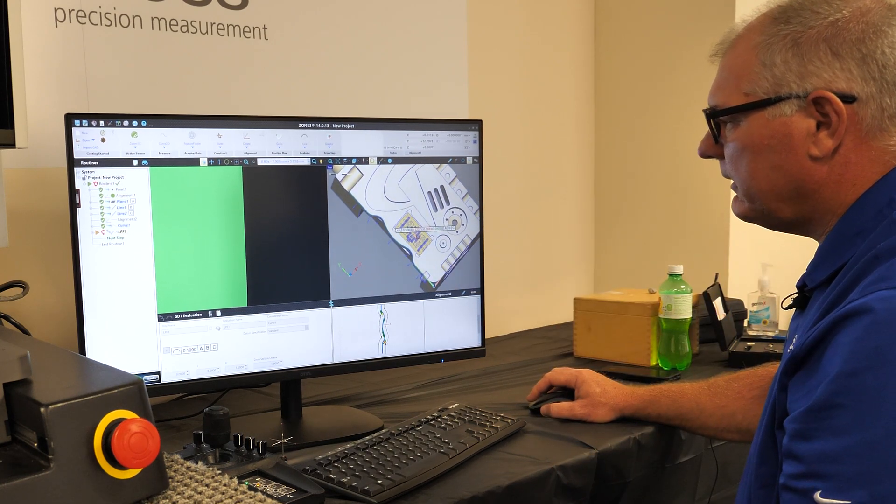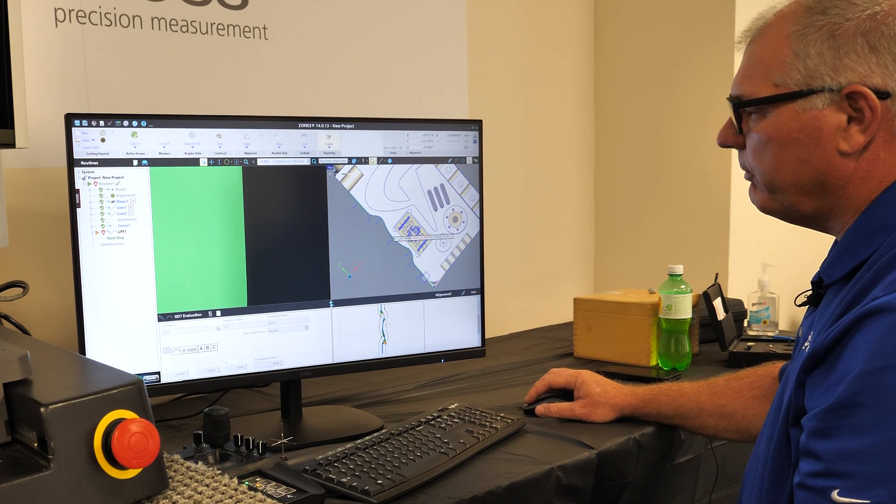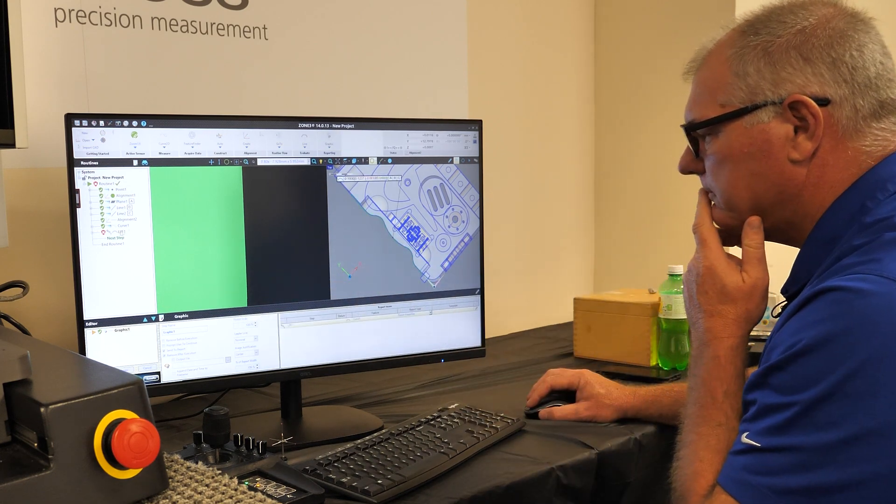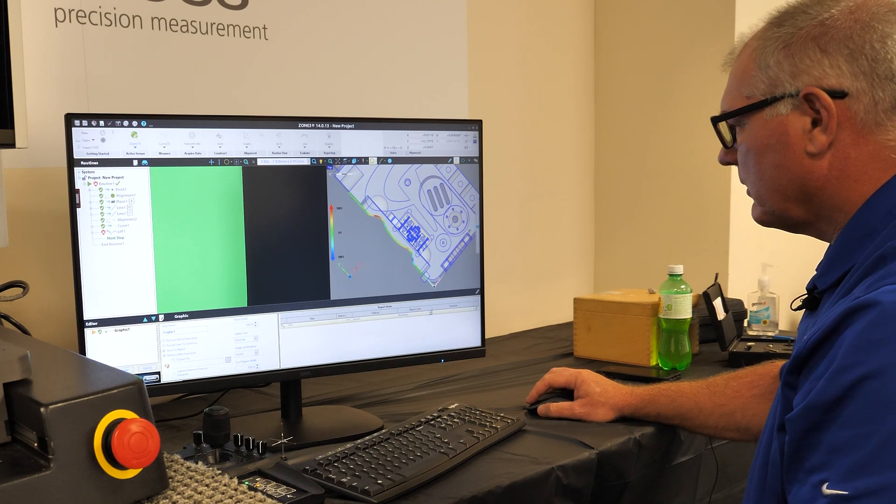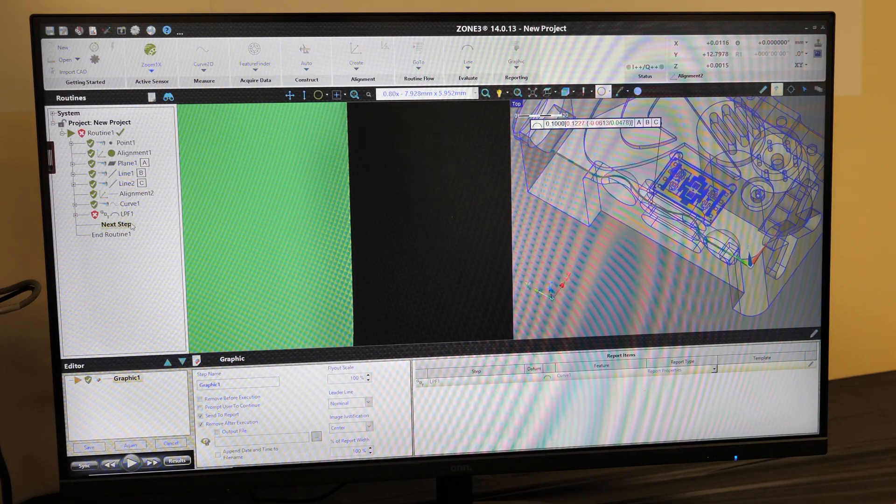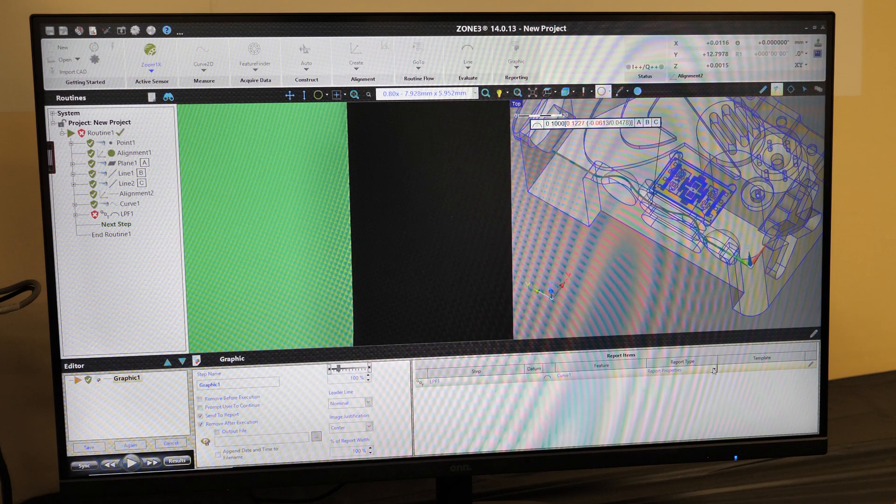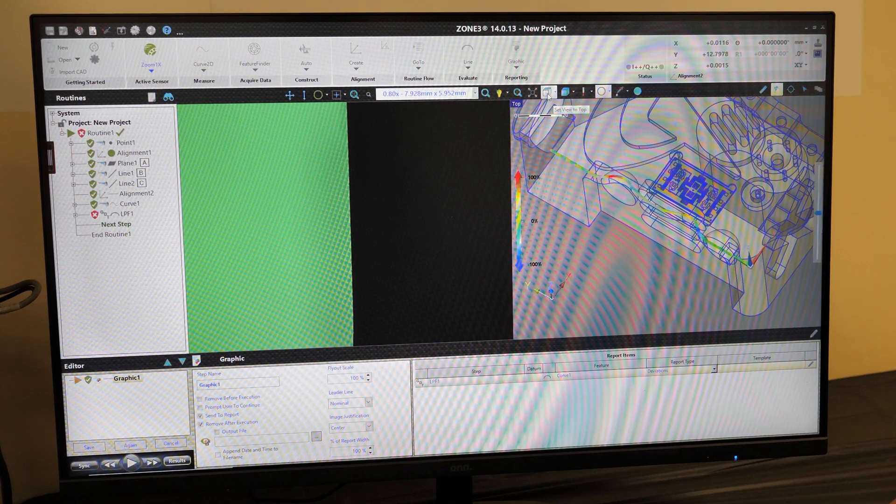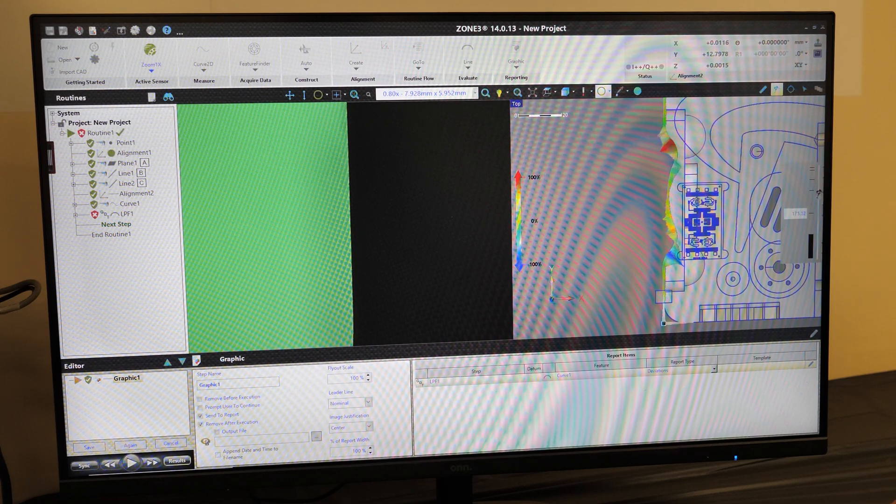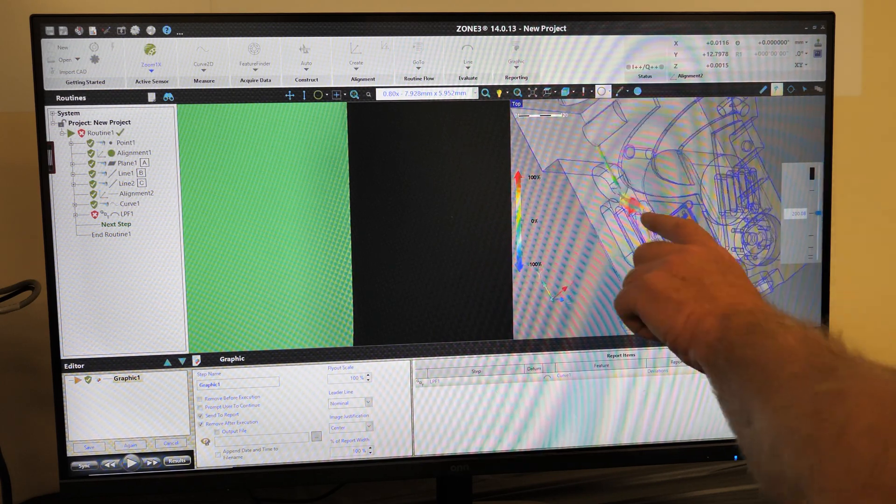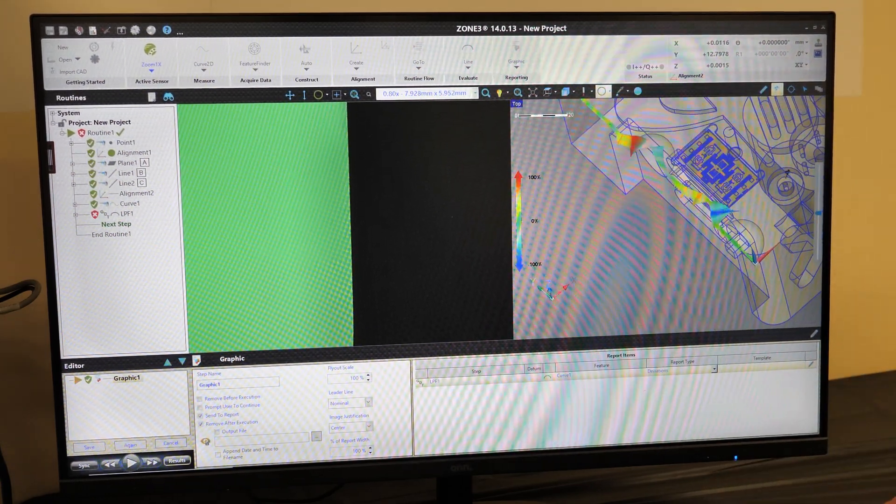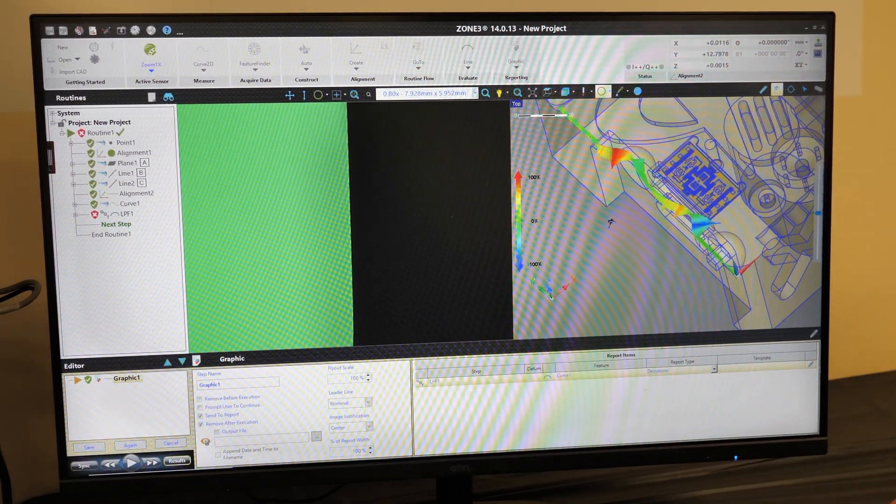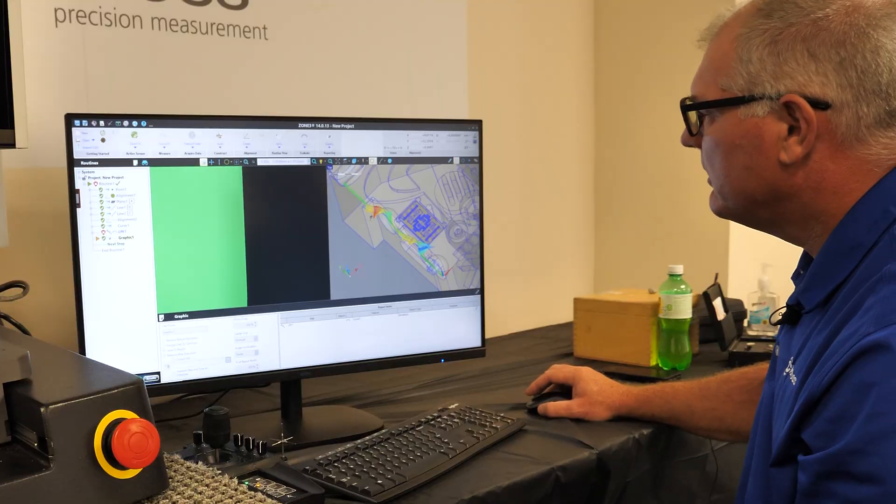We can carry that a step further. We can add a graphic report step to that profile. And here, we can add our whisker charts right over top of the CAD model. We can see that our lines here are in green, and then as our CAD model goes out of specification, we can see where that tolerance band is. That now becomes part of our report.